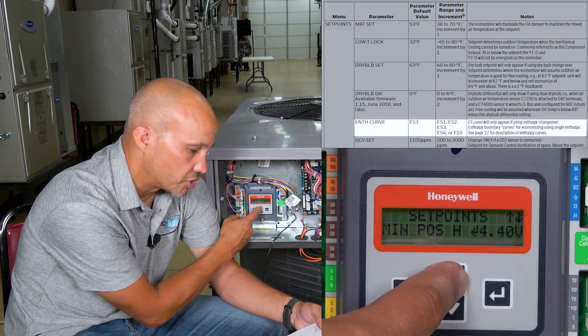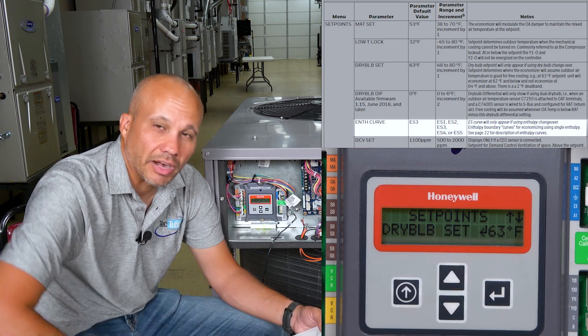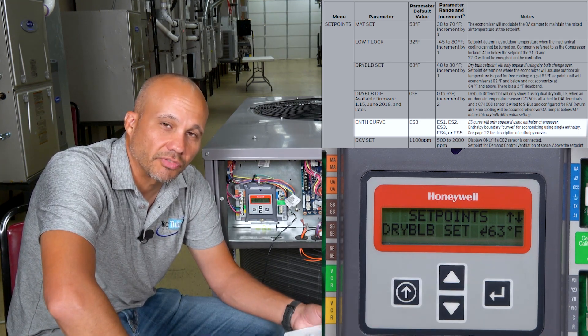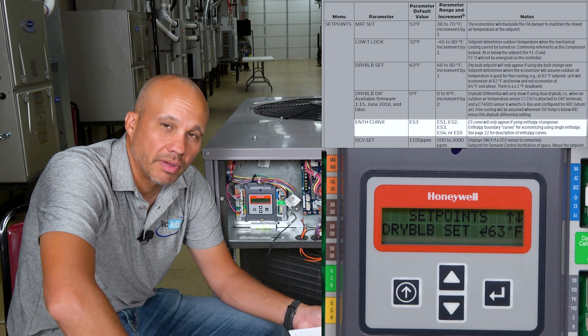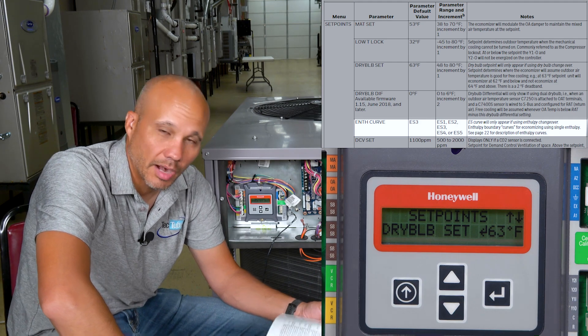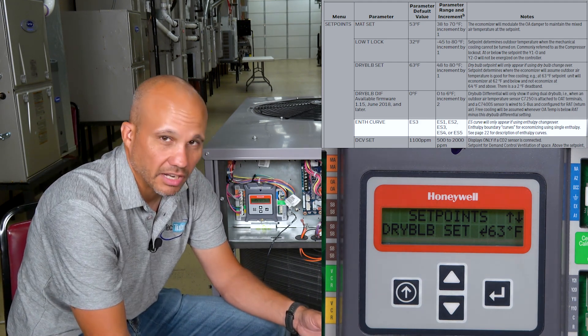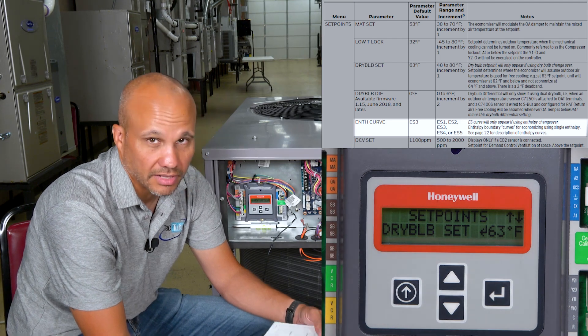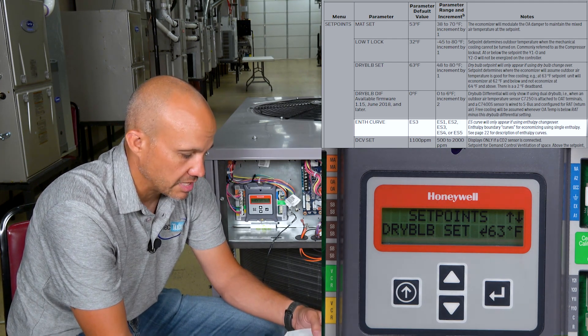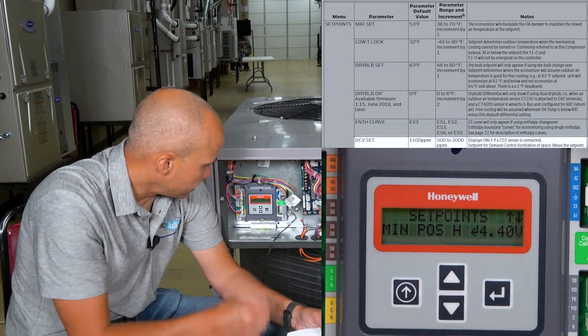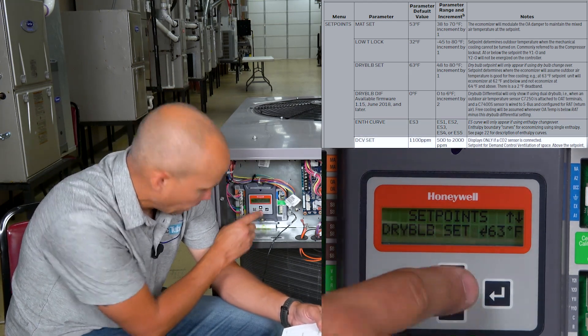Scrolling down would show the enthalpy setting, but I don't have an enthalpy sensor wired so it's not showing. The enthalpy sensor has different curves — ES2 is the curve I recommend. It's the most compliant with energy codes and does the best job: a good balance of taking air that's not too humid without wasting energy. The default is ES3, so I would change that to ES2.